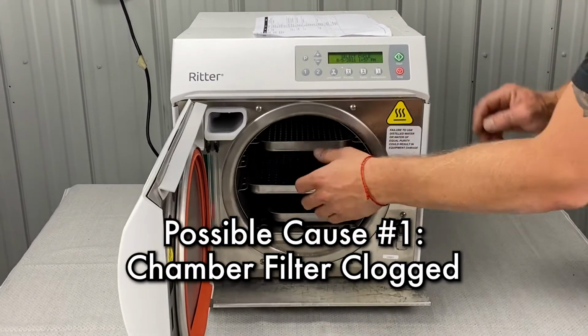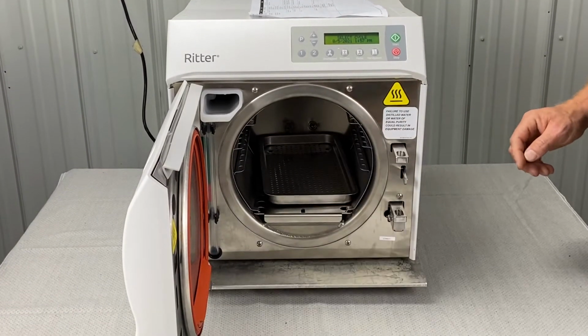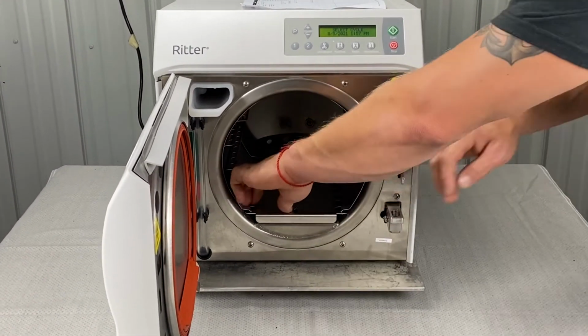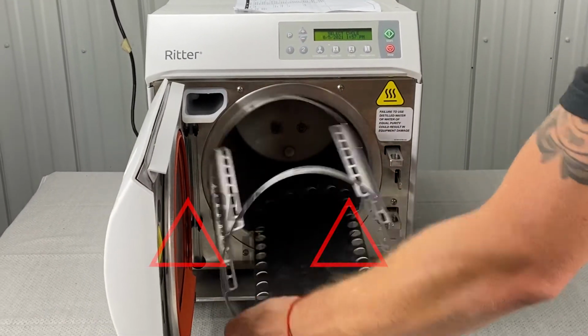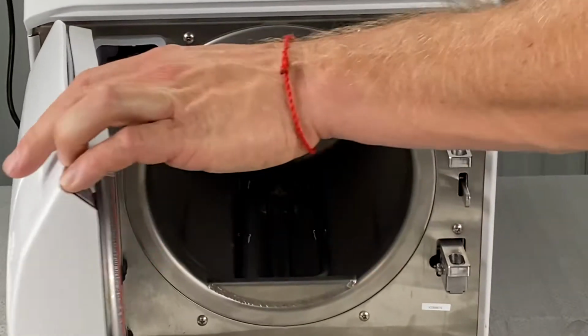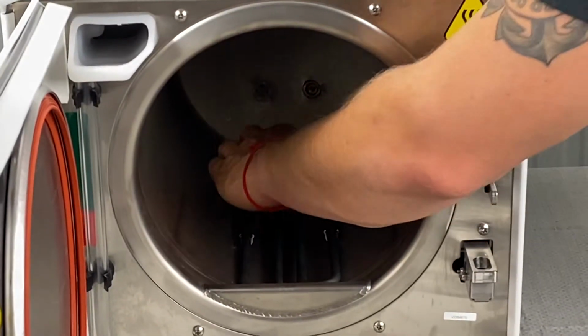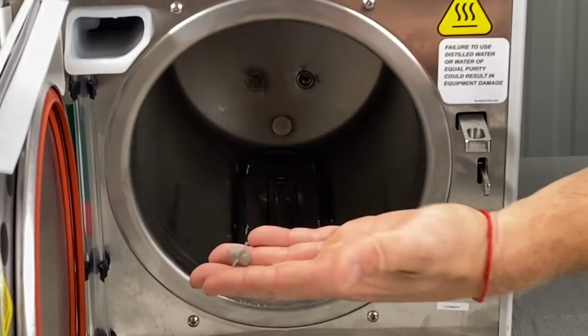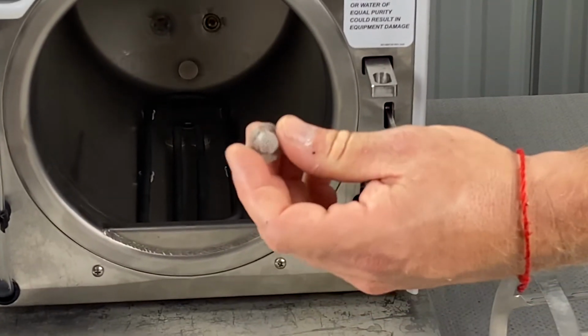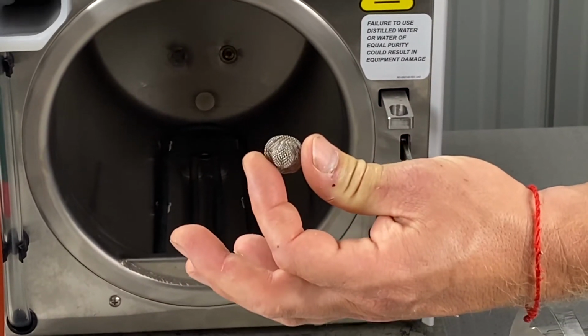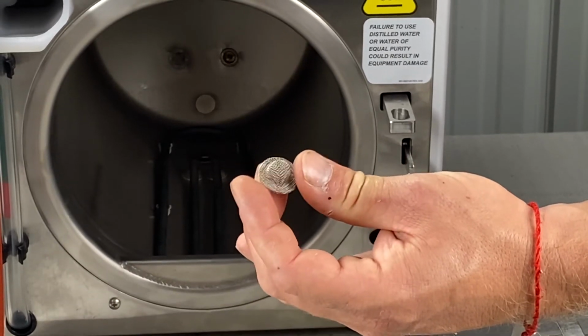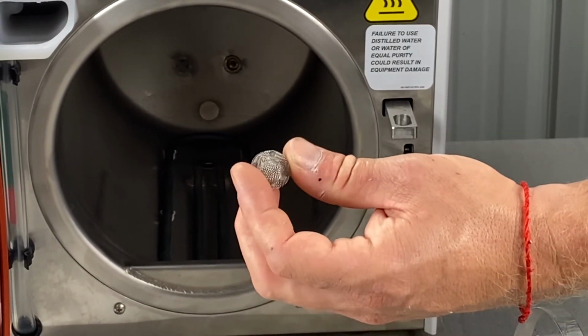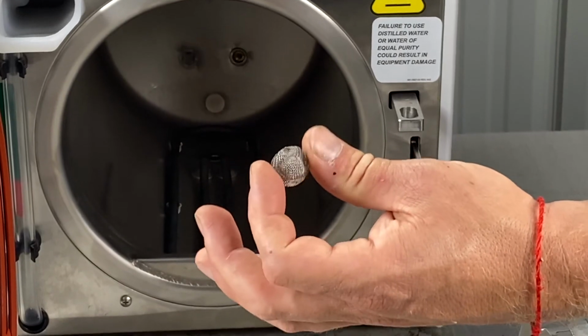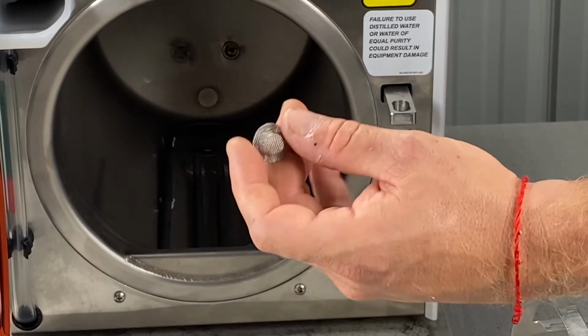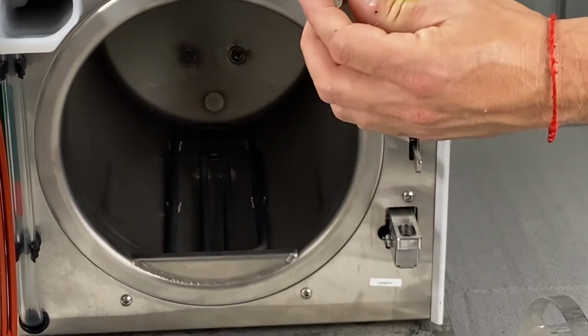So to find the chamber filter, you're going to take all the trays out. Open the door, take all the trays out. Be careful, it might be hot, so give it some time to cool. There's two chamber filters. One is right in the center here. I'm going to pull it out. That's it. It's part of your weekly maintenance. You're going to make sure it's clean. You're going to hold it up to the light, make sure you can see through it. If it's not clean, then you're going to clean it with some speed clean, a toothbrush, some distilled water, or buy a new one. We sell it on the website, statimusa.com.